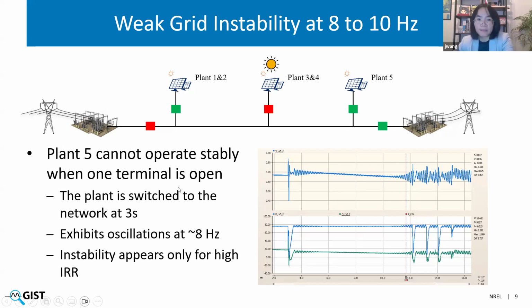And then we ran the stability analysis. We had the full run with all 5 plants online, and we figured out there was an issue with a 6 to 10 Hz oscillation there. After tuning by the inverter vendor, those oscillations are gone. Then we did the line operation with this side open, as you can see here. We found the line instability of 8 to 10 Hz oscillation, and you can see the plots here. They amplified and then sustained there. This oscillation is also aligned with the impedance scan results. So this is what we found from the stability analysis.